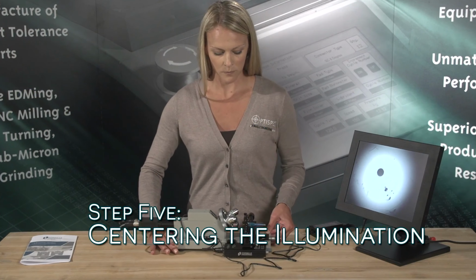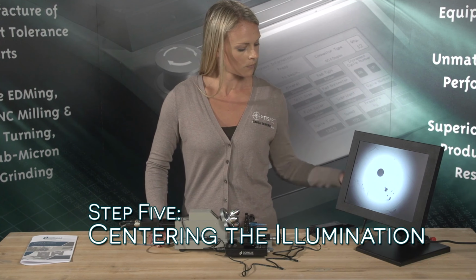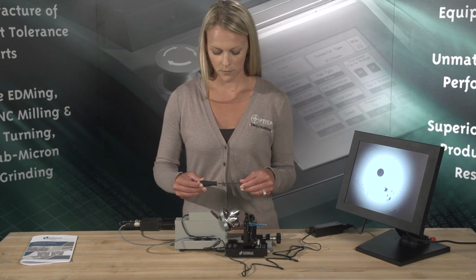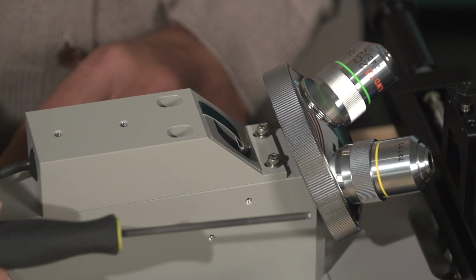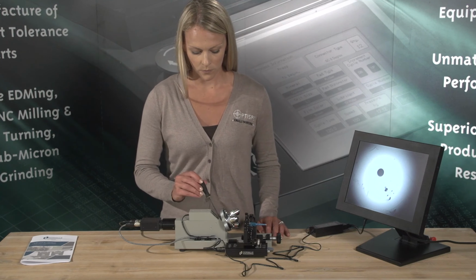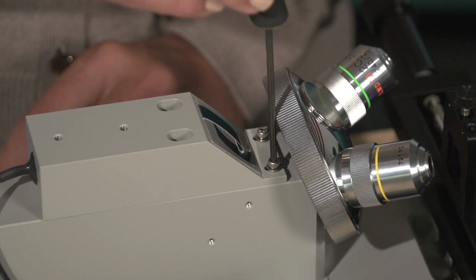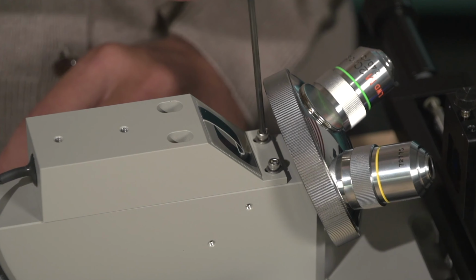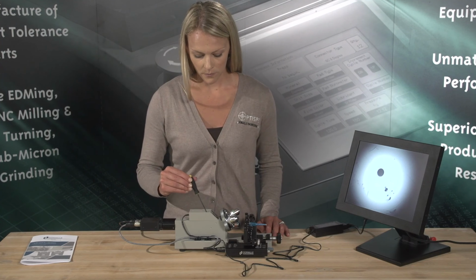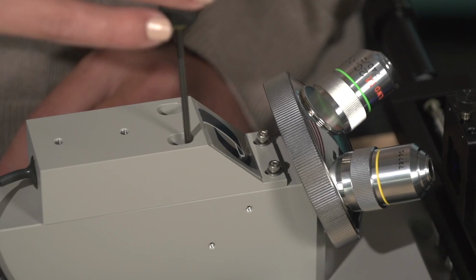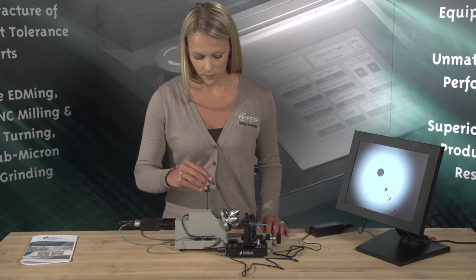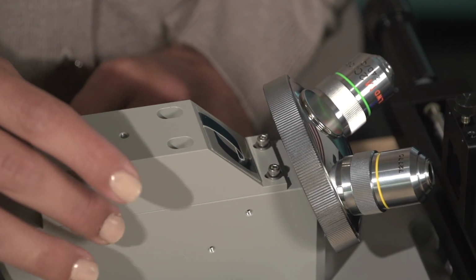Step 5. Centering the illumination. All scopes are set up from the factory, but replacing lamps or periodic cleaning of the beam splitter may require the operator to recenter the illumination. Centering the illumination of the DE2503 is critical in order to maximize performance of the microscope. To readjust the illumination position, do the following.